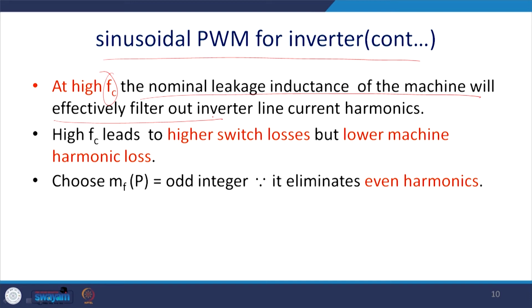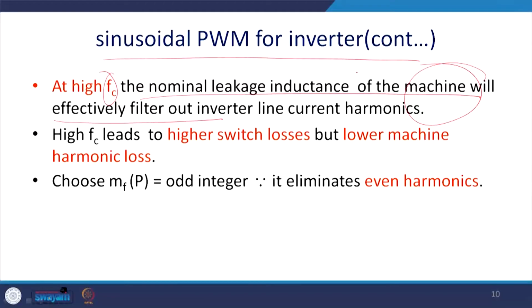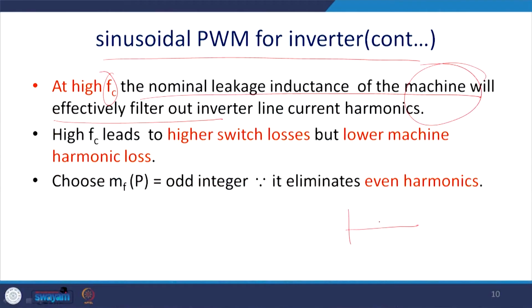So, inductors are present in the line, or you may require to put in small filters, otherwise it will kill the insulation of the machine and the machine life will come down. So, for this reason it is advisable to put a filter before you connect to the machine, so that you apply almost a sinusoidal waveform, because a sinusoidal waveform is best suited for an AC machine.